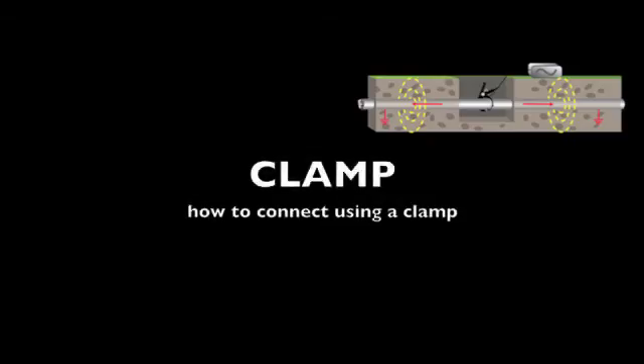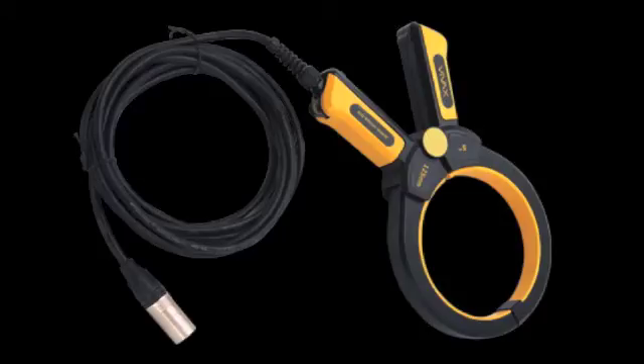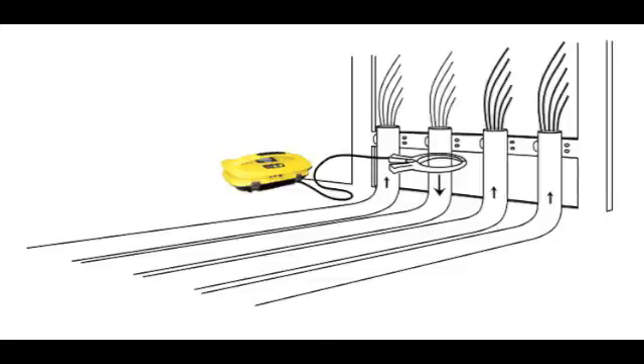If a direct connection to the utility line is not possible, the second way to connect a transmitter is to use a clamp. The clamp's cable will replace the direct connection clips, and there is no ground cable. Clamps are most useful for pipes completely covered in insulation that cannot be damaged, or are an excellent way to connect to headers.